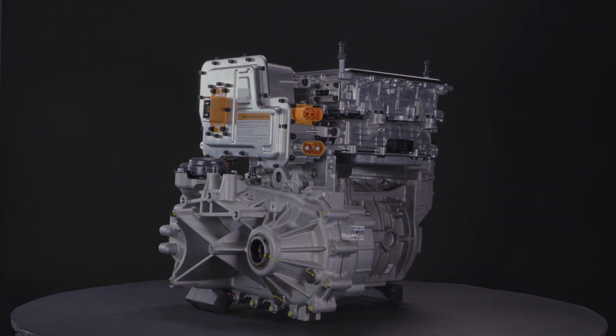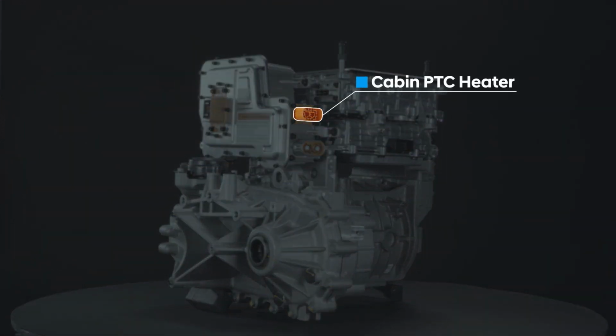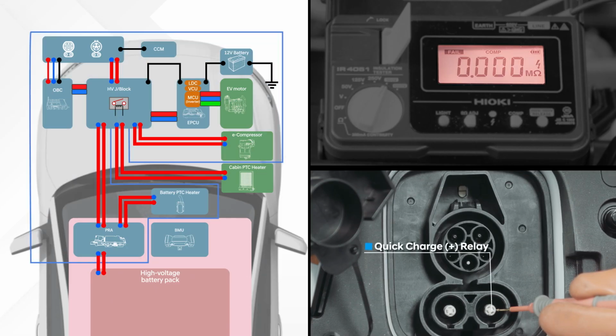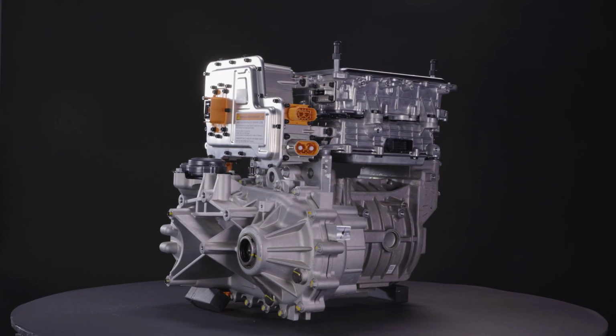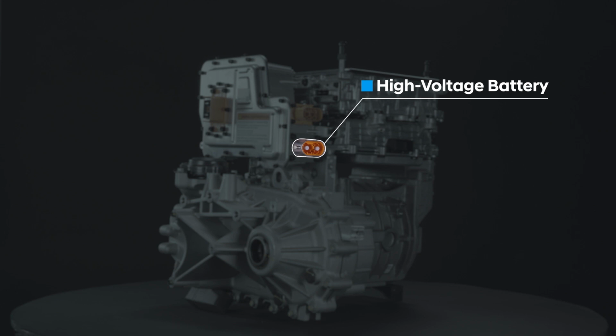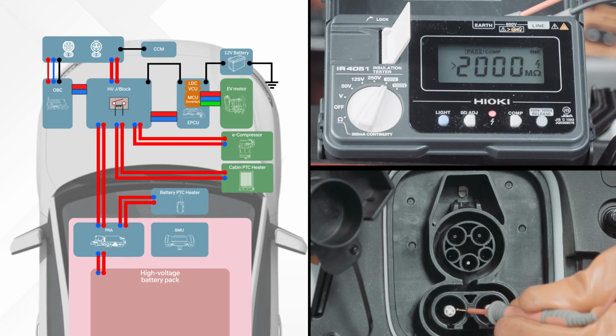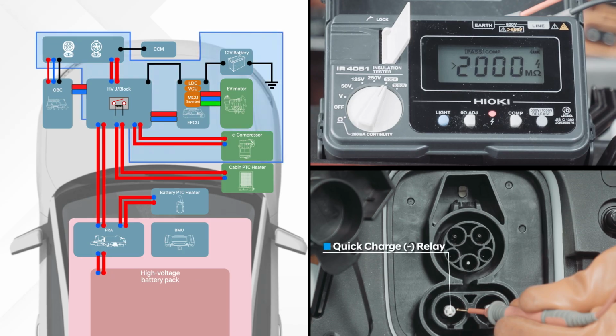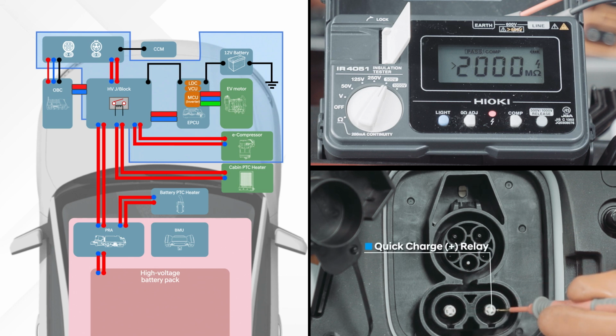First, remove the PTC heater cable on the high voltage junction block and measure the insulation resistance. As a result of the measurement, there is still a problem. Next, remove the high voltage battery cable of the high voltage junction block and measure it. It is measured normally at both charging inlet plus and minus DC terminals. Therefore, there is a trouble between the high voltage battery cable and the rear end of the PRA main relay.